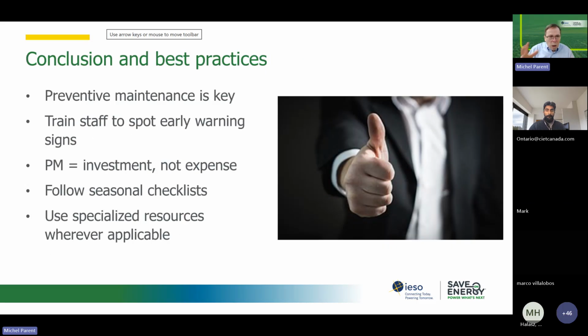So I know we went quite fast. There's a lot of different issues that can pop up in the building. We will provide you with that tool, that little Excel tool, along with the test that you can do if you've got a VAV box. And remember, the PM program is at the basis of all what we saw. How to avoid having the failure is to have the PM program. The PM program needs to address a lot of what we saw today to intercept that before it becomes a problem. And it's not an expense. It should always be seen as an investment.